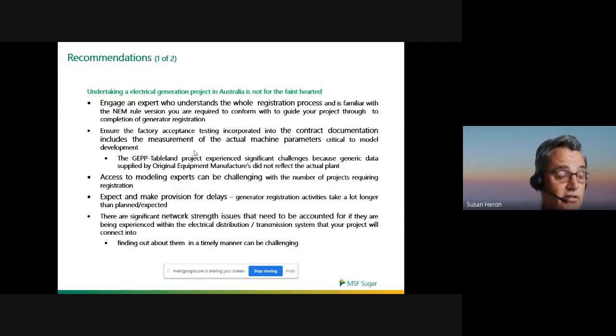Ensure the factory and its systems are tested. If I did this project again, these are things I'd pay much more attention to upfront - make sure you actually factory acceptance test it, and measure all the machine parameters so they're available for your modelling, which greatly reduces the risk of getting them wrong.